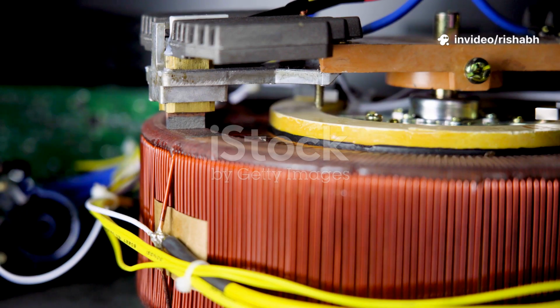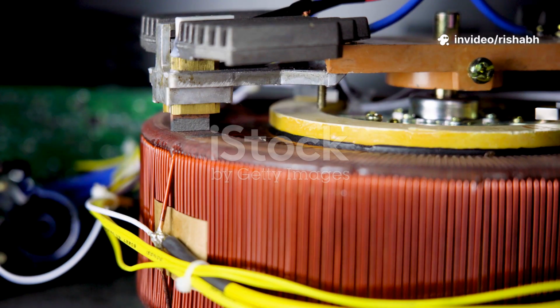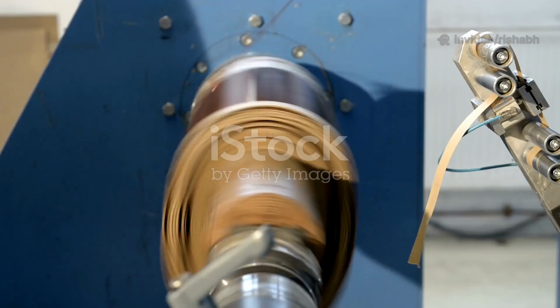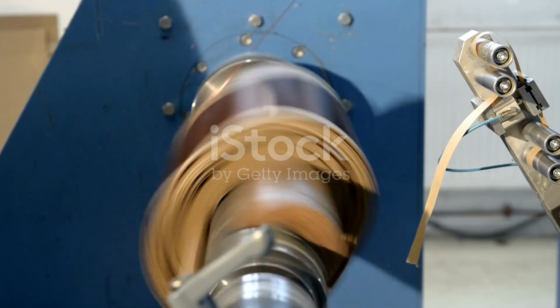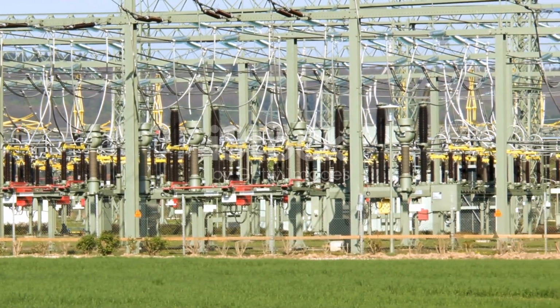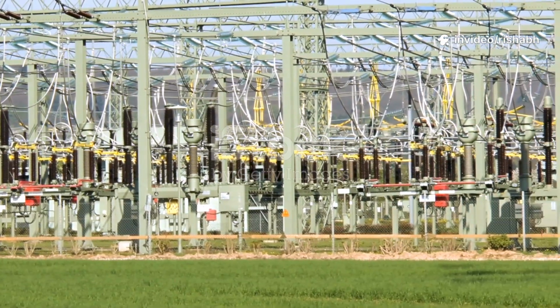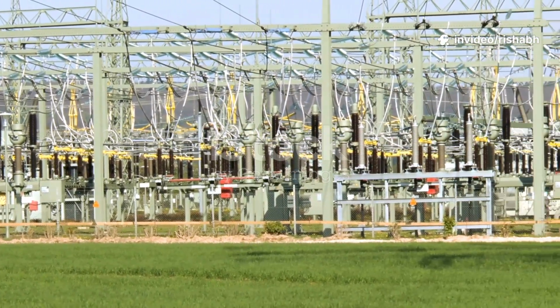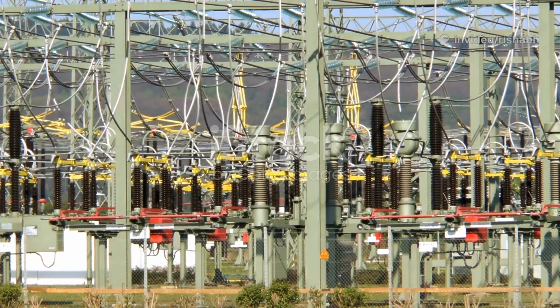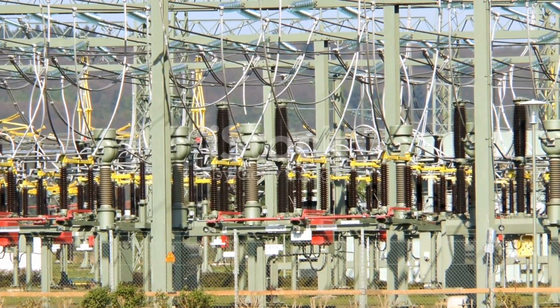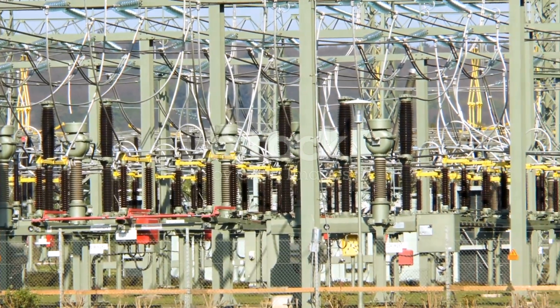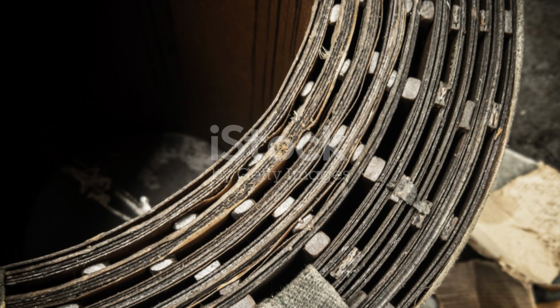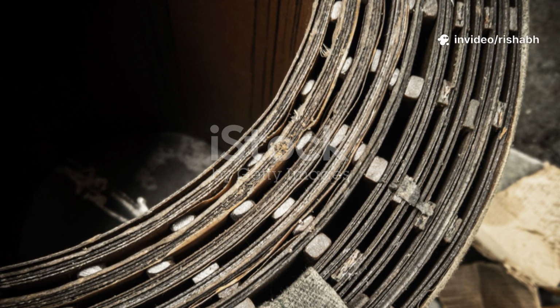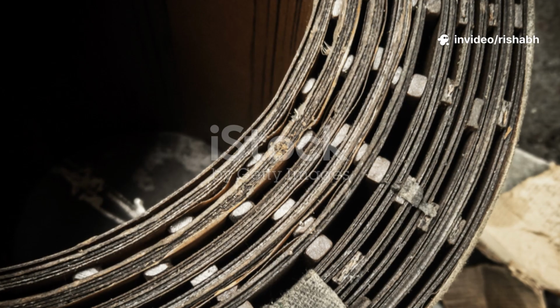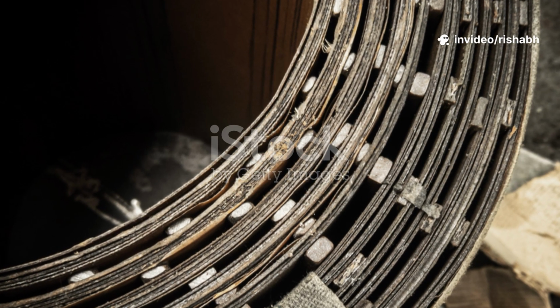Its lower voltage means it requires less insulation from the grounded core. The high-voltage winding is then wound concentrically over the low-voltage winding. This arrangement is mechanically strong and helps to control the immense electromagnetic forces that arise during a short circuit. These forces can be powerful enough to physically crush the windings if they are not designed and supported properly. The space between the windings is precisely controlled, filled with insulating barriers and oil ducts to ensure electrical integrity and allow for cooling.